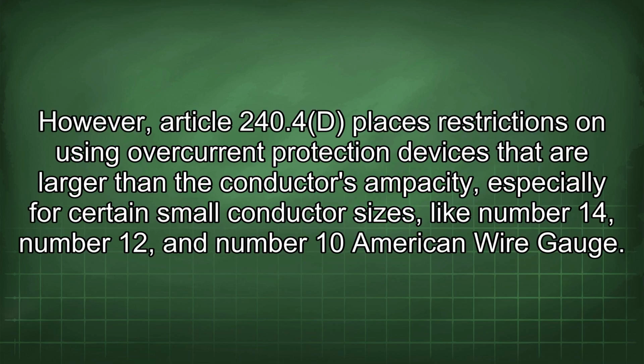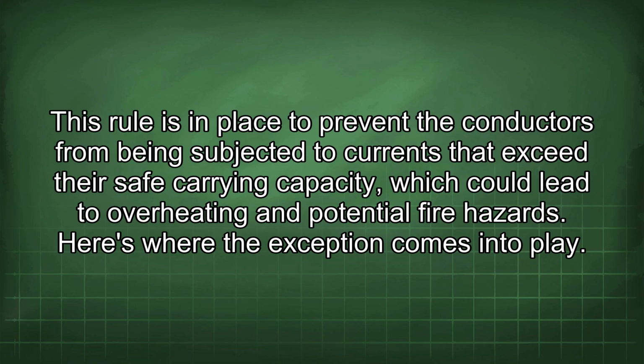However, Article 240.4d places restrictions on using overcurrent protection devices that are larger than the conductor's ampacity, especially for certain small conductor sizes, like number 14, number 12, and number 10 American wire gauge. This rule is in place to prevent the conductors from being subjected to currents that exceed their safe carrying capacity, which could lead to overheating and potential fire hazards. Here's where the exception comes into play.